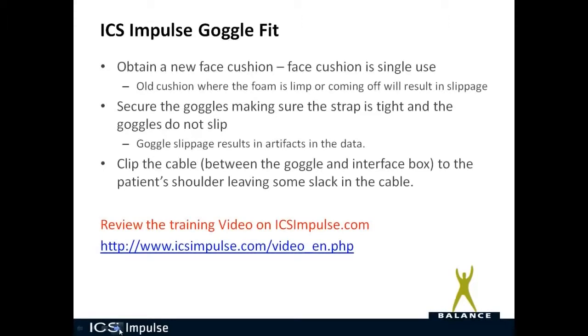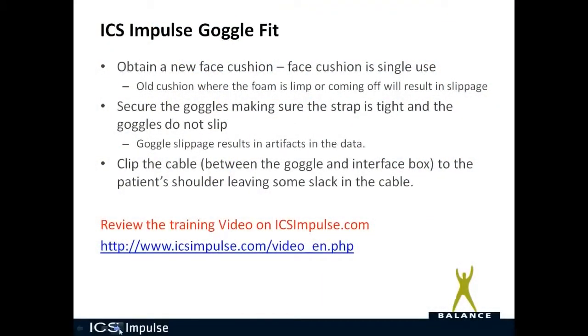Let's talk about goggle fit. When you get ready to place the goggles on the patient, you need to make sure you obtain a new face cushion — it is single use only. If you've reused the face cushion and it looks limp or the foam is not adhering to the plastic insert, this will result in slippage. You need to make sure the strap is tight and the goggles do not slip, as goggle slippage results in artifacts in the data. Also clip the cable from the goggles to the interface box onto the patient's shoulder or collar, because pulling on an unclipped cable can cause goggle movement and slippage.